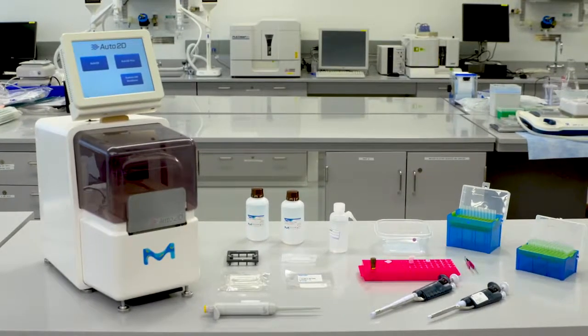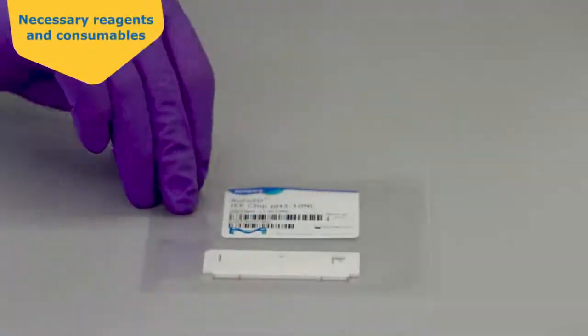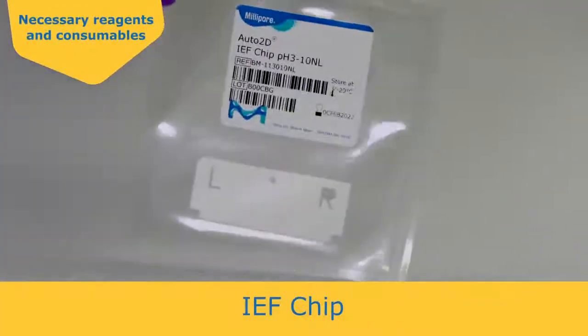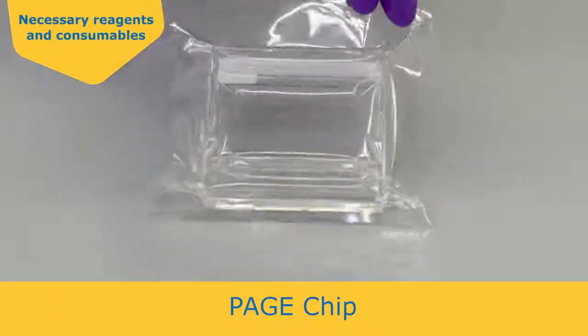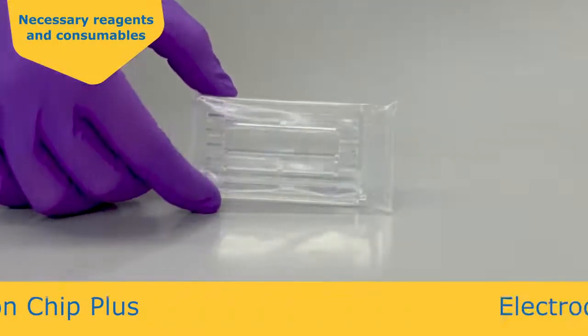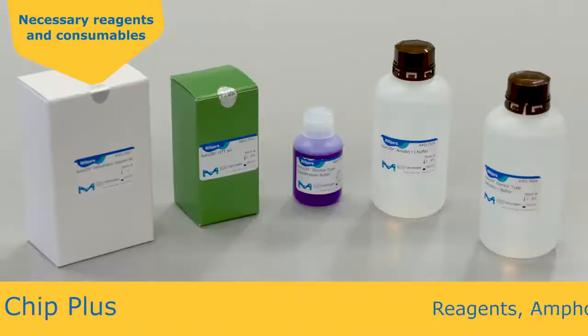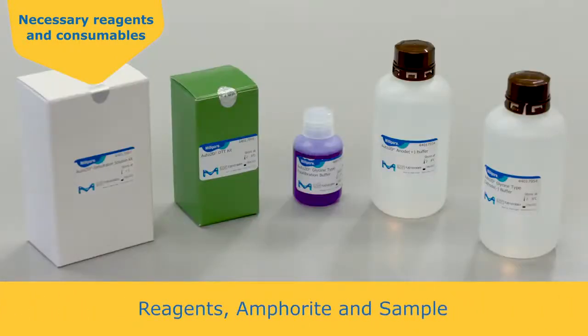First, gather all of the supplies needed to run the Auto2D device, including the IEF chip, PAGE Chip, Solution Chip Plus, Electrode Chip Plus, reagents, ampholyte, and protein sample.